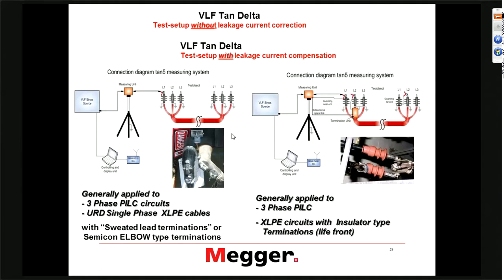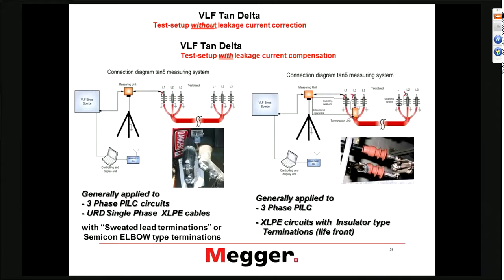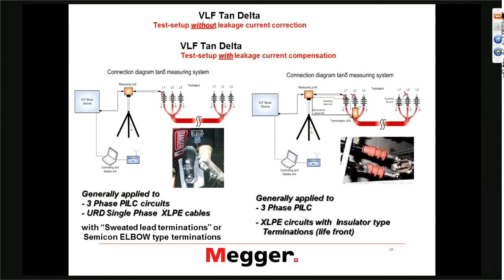The performance criteria in IEEE 400.2 are not very tight — they are all in a magnitude of 10 to the minus 3. If I wanted to go down to 10 to the minus 4, that is not required according to IEEE. That's why basically nobody does this type of measurement in the field.